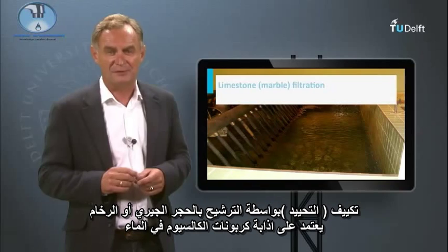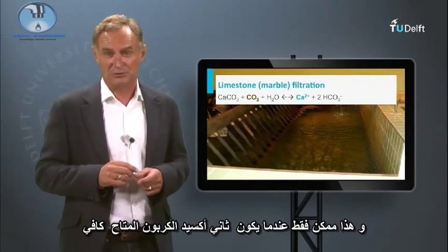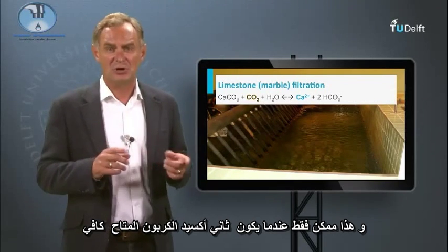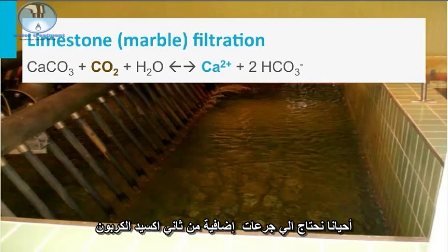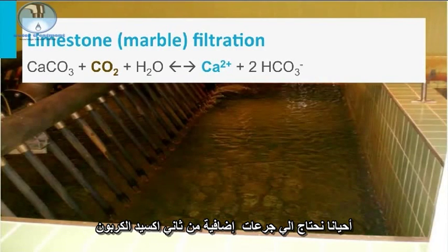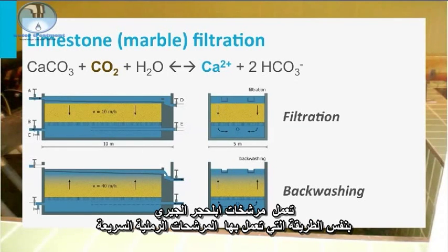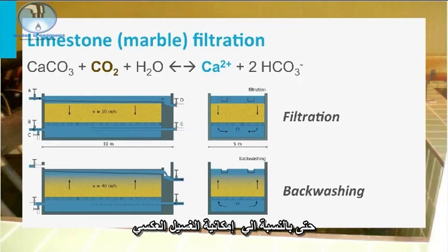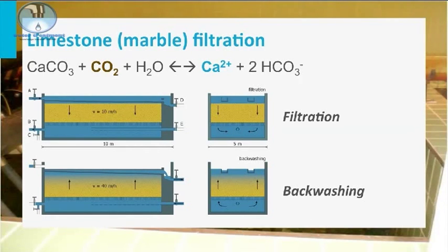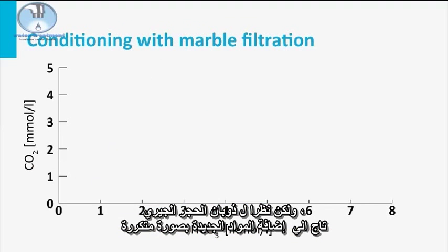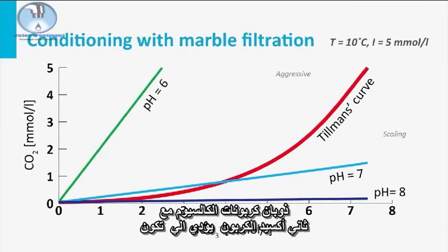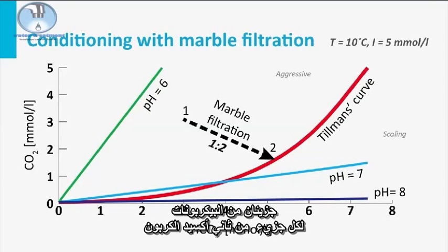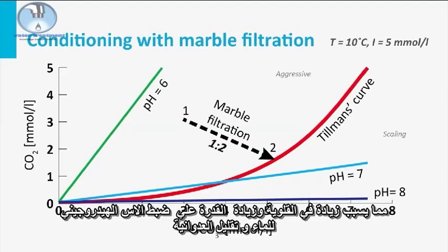Conditioning with limestone or marble filtration is based on the dissolution of calcium carbonate in water. This is only possible when sufficient carbon dioxide is available; sometimes additional carbon dioxide dosing is required. Limestone filtration is performed in the same way as rapid sand filters, including the possibility for backwashing. However, due to the dissolution of the limestone, frequent addition of new material is needed. The dissolution of calcium carbonate with carbon dioxide results in the formation of two moles of bicarbonate per one mole of carbon dioxide, increasing the alkalinity and buffering capacity of the water and decreasing the aggressiveness, bringing the water into chemical equilibrium.